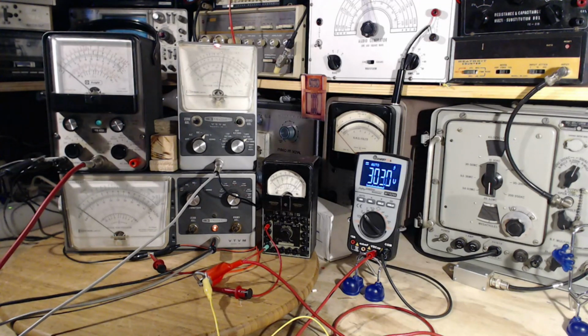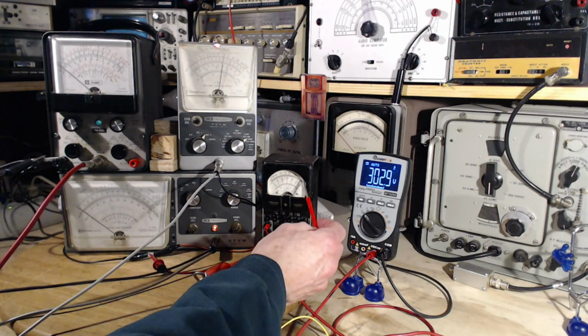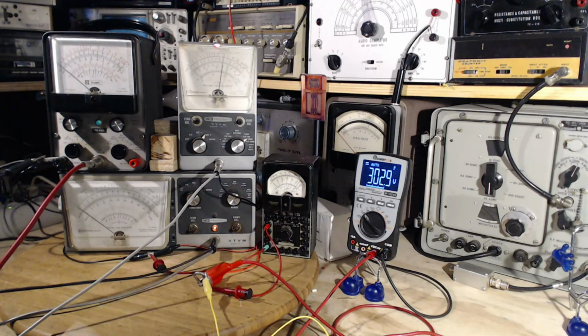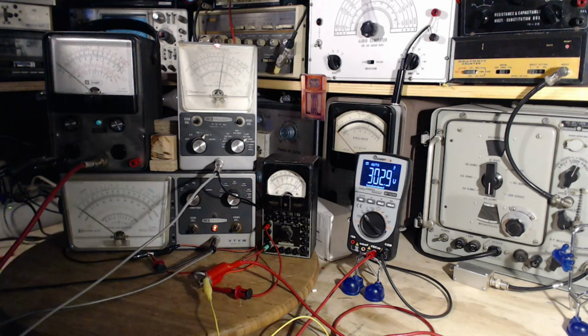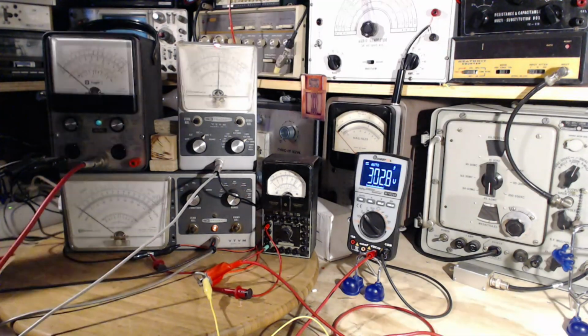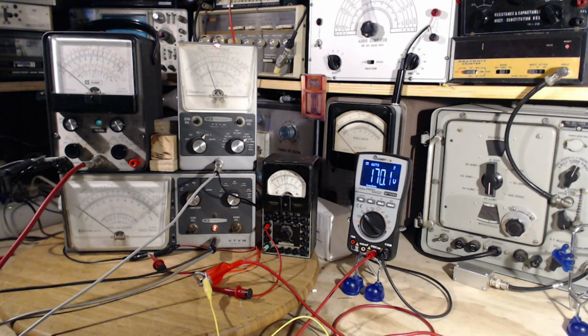Just making sure the pointer's not stuck there. So he's low because 300 is right at the top of the scale here. Okay, now that's it for the DC calibration. Let me get rid of this high voltage before I'm fried. The next thing on the hit parade here for these meters is AC calibration.